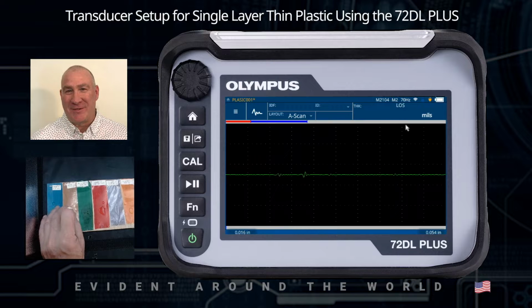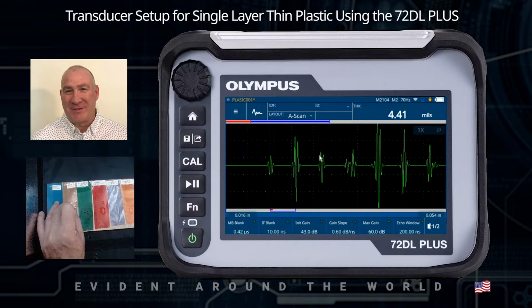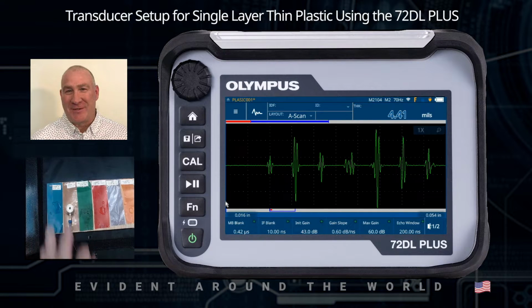This was supposed to be reading about 4. I'm going to make sure I have water on the surface. Okay. And the other thing we want to do is finish up the adjustments, and I want to check a couple other things. So at this point, what I can do to make it easy on myself is freeze the display. Underneath the Cal key is a play pause key, and if I press that, I'm going to pause or freeze the display. You can see up in the corner here, the little F is displayed, letting me know that this is frozen. A nice feature about this instrument is that because we digitally capture the entire waveform and all the parameters, we can make adjustments to it without having to have a live signal.